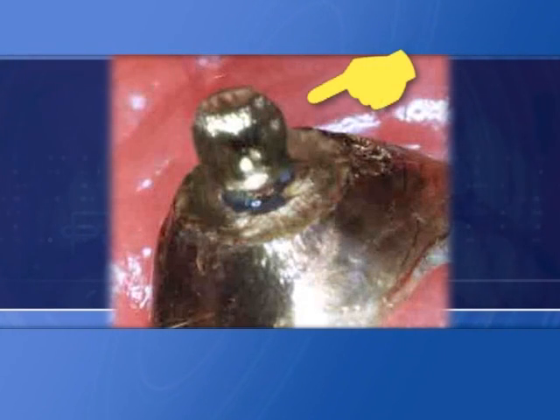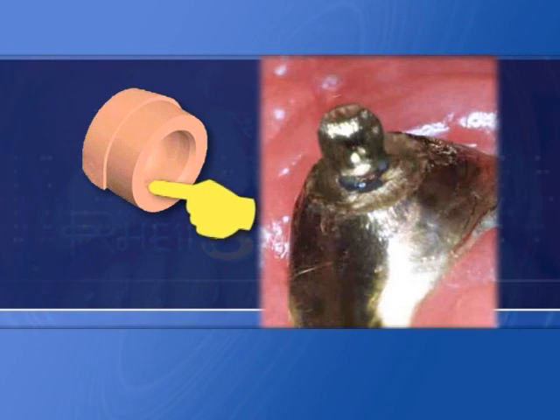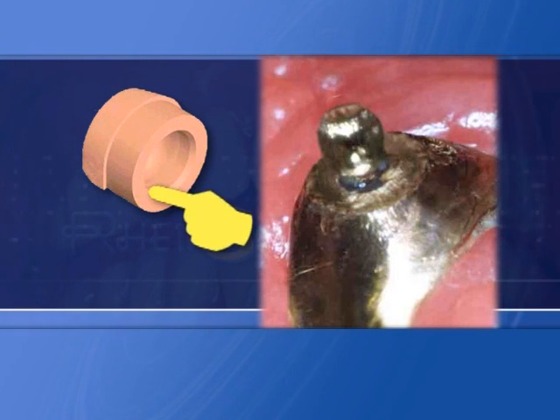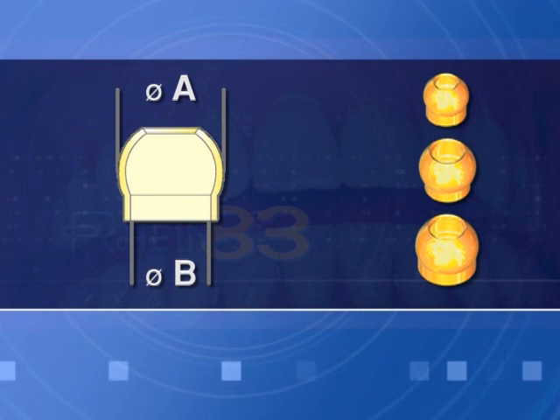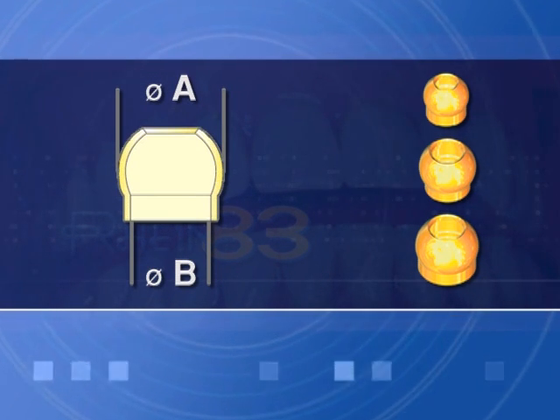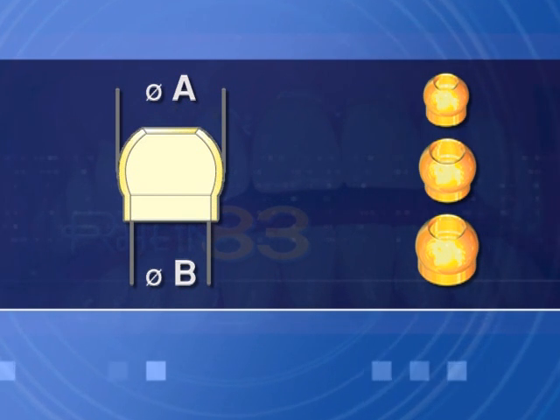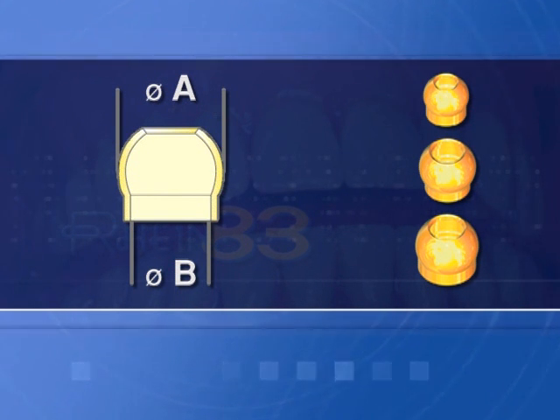When wearing out is minimal, undersized tight caps, code DR8, can perform well to give back enough retention. Even when the sphere is almost totally worn out, it can be repaired and brought back to a new and original dimension using a titanium plus tin coated concave sphere to be cemented over the old one.